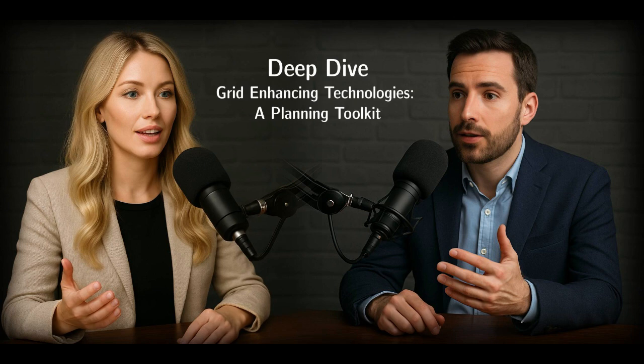Then you have series devices like thyristor-controlled series compensators, TCSCs. TCSC, okay, series compensation. Right. These provide variable series compensation, maybe 0 to 70% of the line reactance. Again, very fast millisecond response to disturbances. What does that allow you to do? It gives you continuous control over the line's impedance. You can effectively make the line look shorter electrically, allowing more power to flow. They integrate with protection systems too.